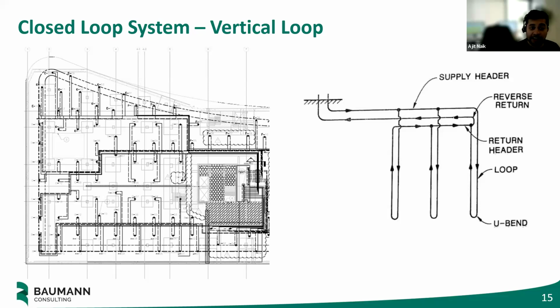These work a lot better than any of those horizontal distributions just because you're going down. You're less impacted by the sun, less impacted by the surface temperature. 100 feet down, 200 feet down, the temperature is much more steady and much less impacted. If you penetrate through groundwater, sometimes you can take advantage of that - it's not quite as good as an open loop system, but if you've got a closed loop in an aquifer that's washing your pipes all year round, hey, great.